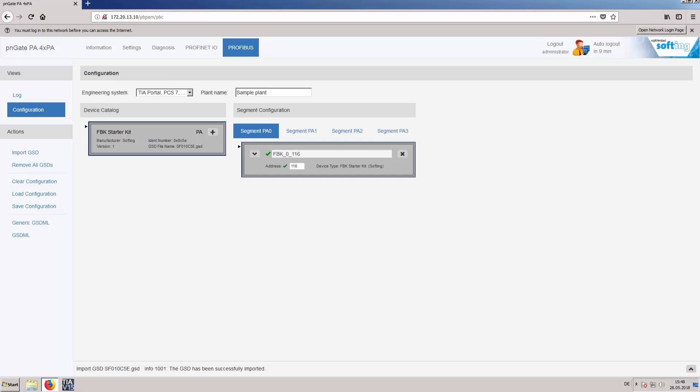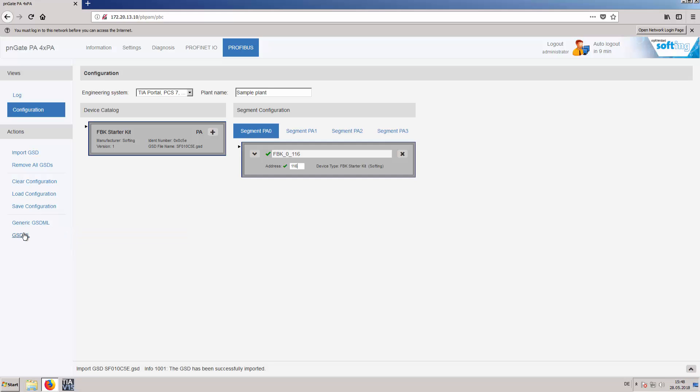There are two possibilities to create a GSDML file. One, using generic GSDML the user can create a more flexible GSDML file which can be imported into the engineering system. After that, the IO module configuration has to be done in the engineering system.